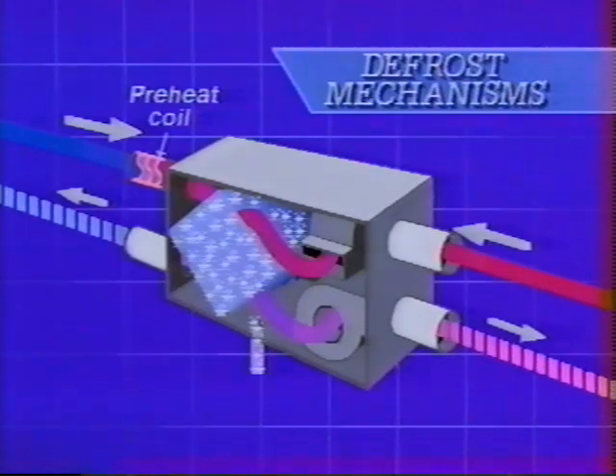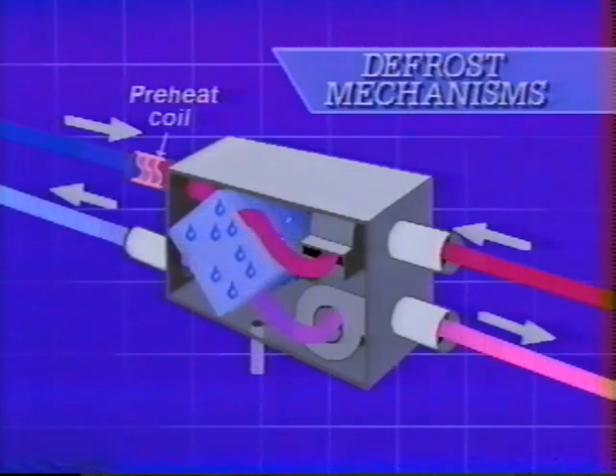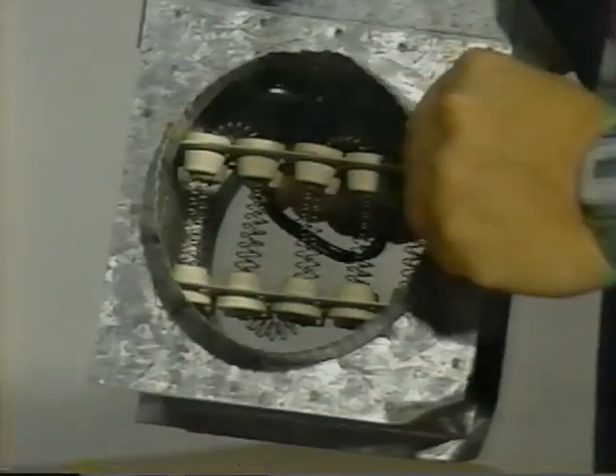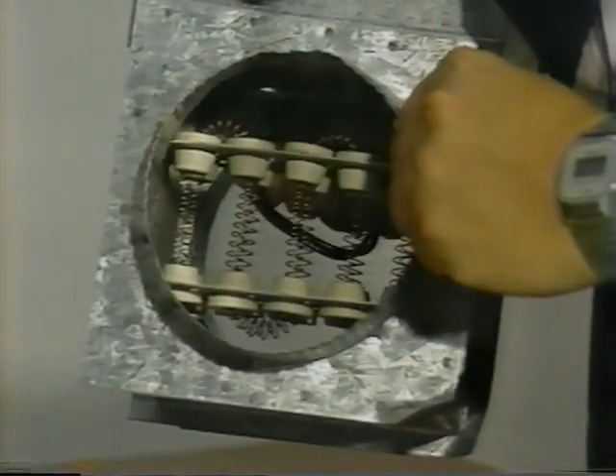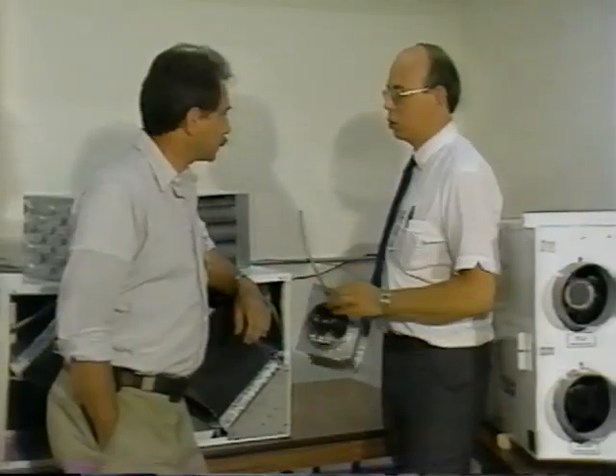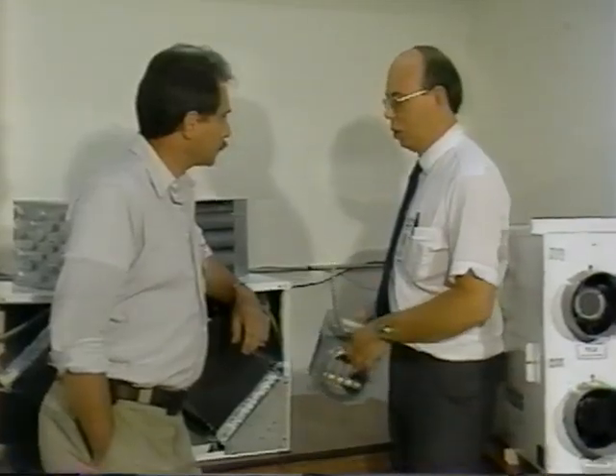Back in behind this plate here is an electric heater which heats up the air. What it does is make sure that the outdoor air coming in is heated up so that when it hits the core, it doesn't cause any frosting. And presumably you also have to look at the energy requirements for these preheaters as well when selecting a unit. That's right. If you have a lot of cold weather, these can use a substantial amount of energy.